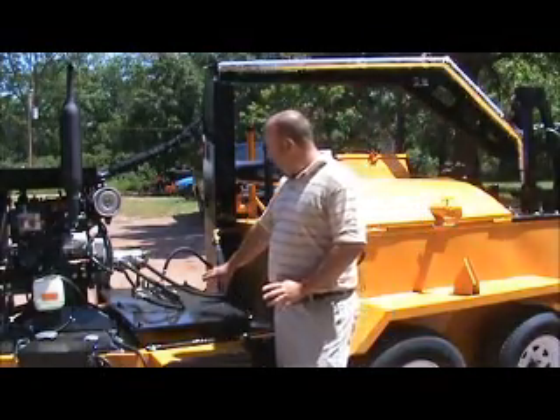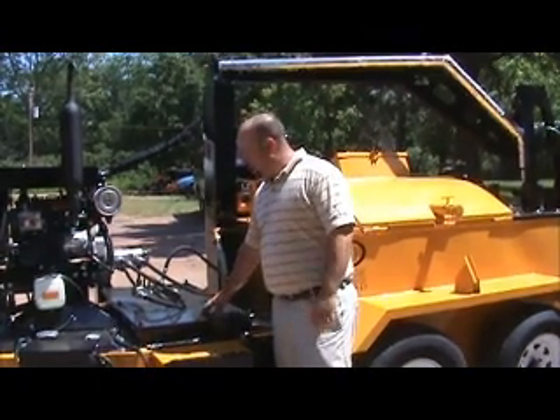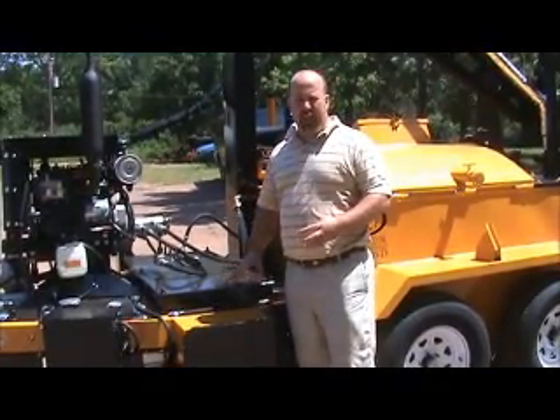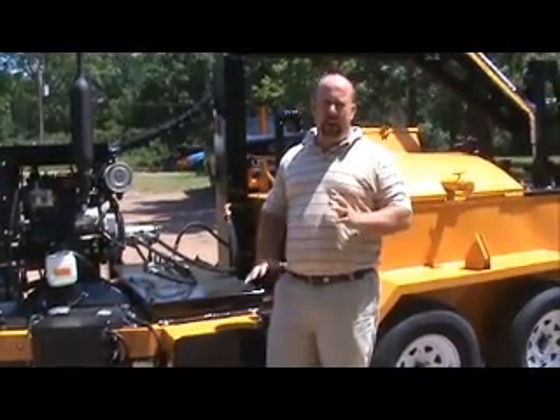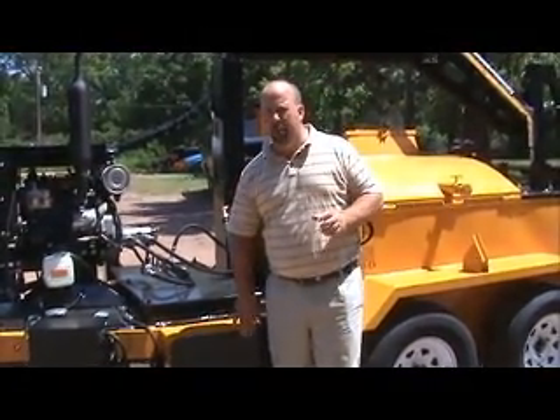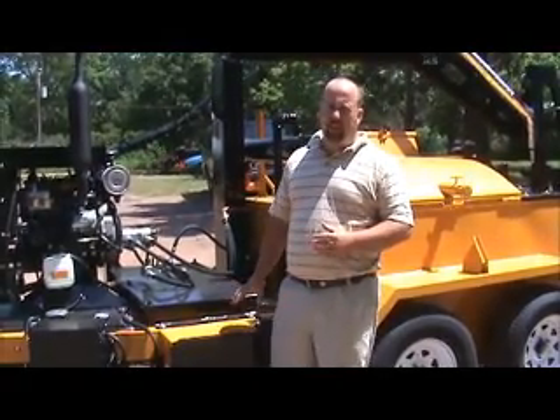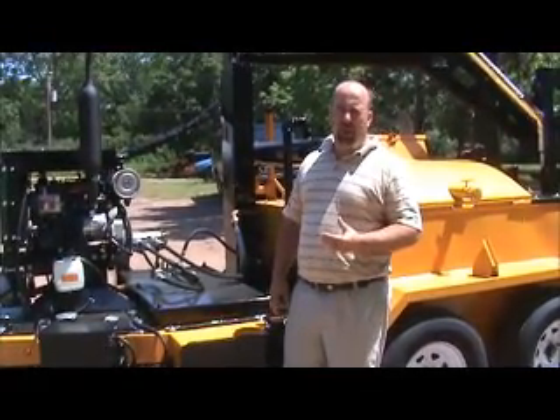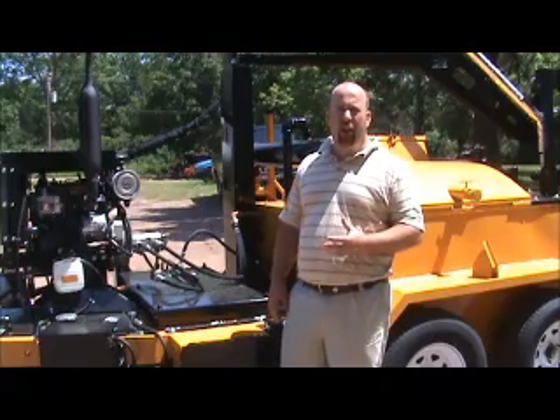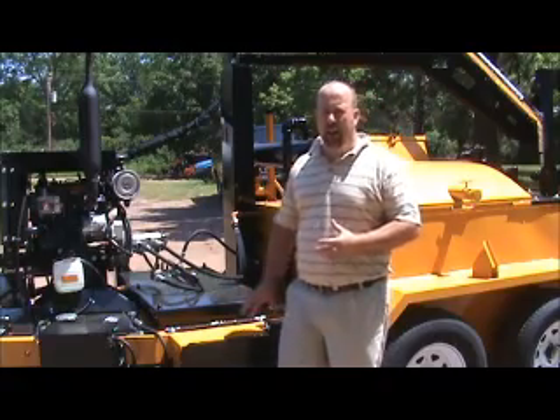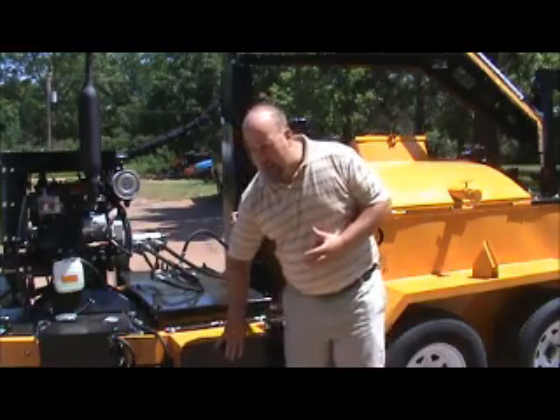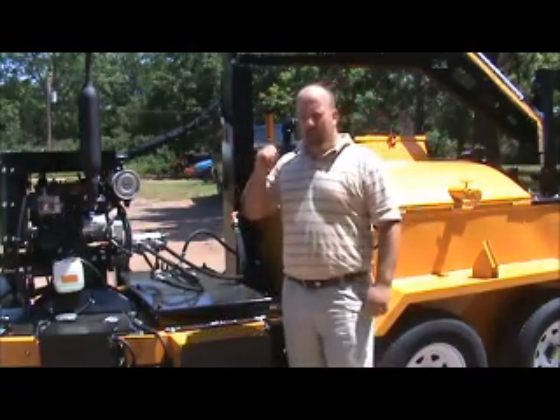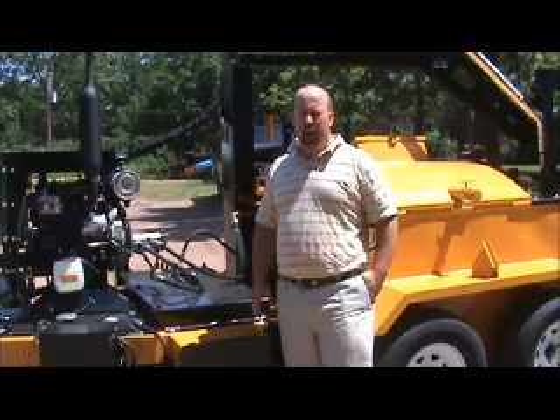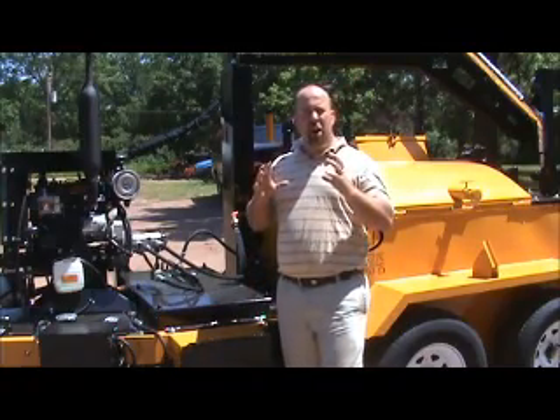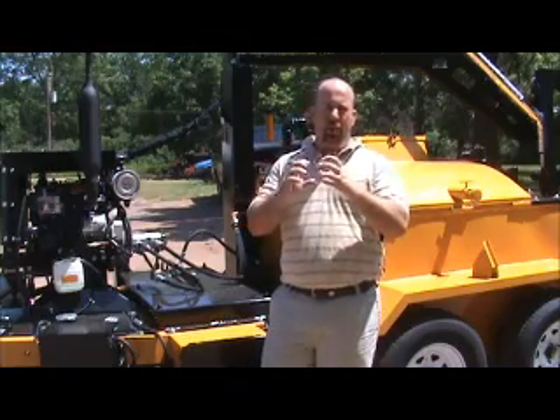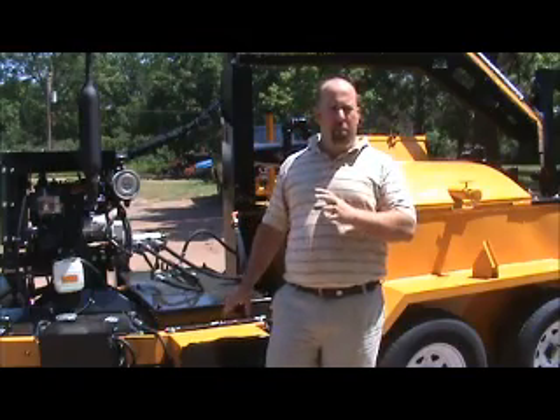So our burner fires through this inner heat exchanger box, and the inside of that heat exchanger box is actually a stainless steel liner. Now we require you guys, and in the manual there is a maintenance procedure, that you do need to maintain that stainless steel liner. Depending on usage, we tell the guys anywhere from 2 to 3 times a year to inspect that. To inspect that, you take the cover off the box, you pull the burner, there's 4 nuts to pull the burner, you can stick a flashlight in there and inspect that stainless steel liner. When you inspect the stainless steel liner, if you notice that there's holes or the liner has started to warp and collapse, it's time to replace the liner.